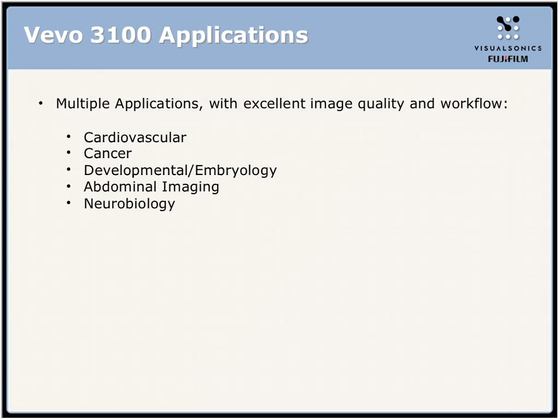One thing I do want to highlight is there are transducer-specific applications. So what that means is on the very first touchscreen layout that I showed you, one of the first slides that I showed you today, it's very application dependent in that for a particular transducer, that was a 25 megahertz transducer that was connected, you could see all of the appropriate applications used for that transducer. That then leads into a number of different presets, and they're all specific by animal type and anatomy. So right off the bat, when you start imaging with the system, for a particular transducer, you know the applications that you should be attempting with it. If you don't see your application there, chances are you aren't using the right transducer. You should either be switching or contacting VisualSonics to find out more about other transducer technologies that may be better suited for the application.